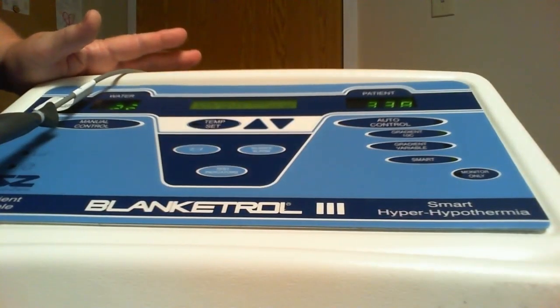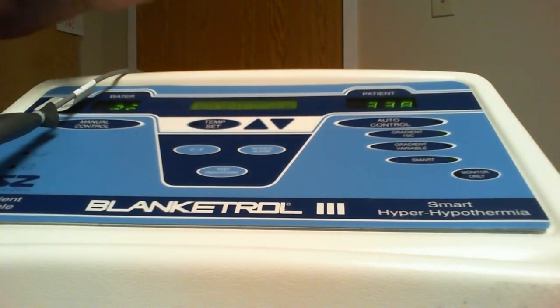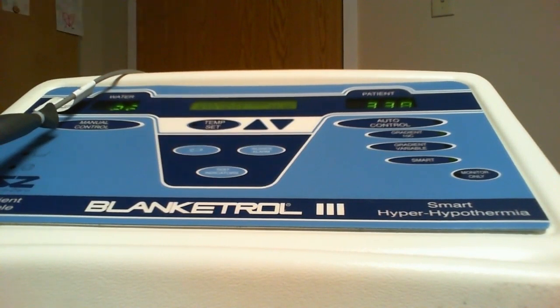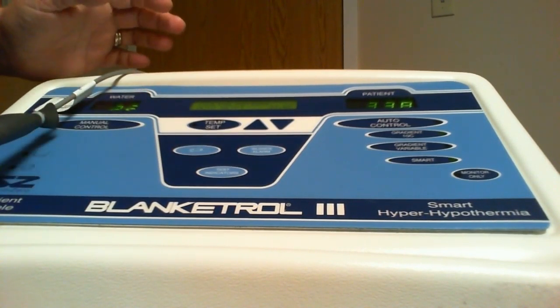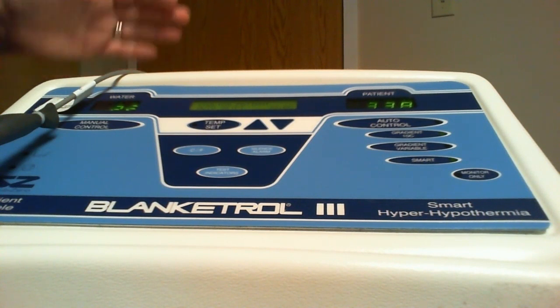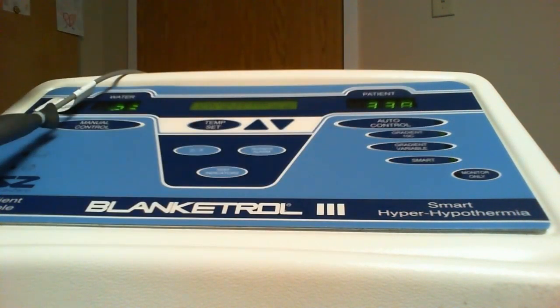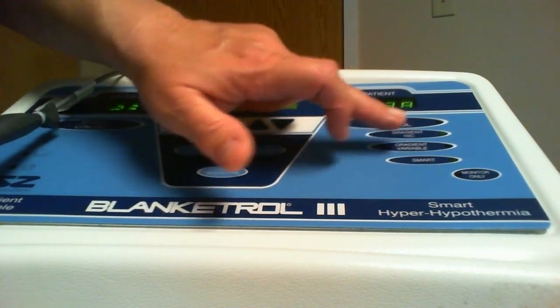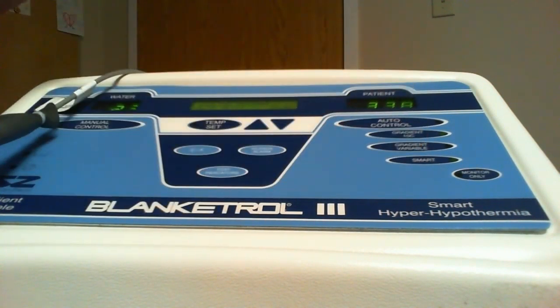And if you remember from the previous video, the reason why we're doing that is so that the water temperature here is never more than 10 degrees away from the patient, either above or below. And we use the smart mode button. We can only use smart mode when we use gradient 10 or gradient variable.